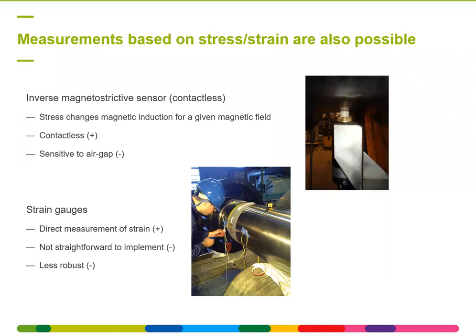Typically, the sensor needs calibration, and this is typically done when going from full speed no load to nominal power. Then you go from zero torque on the shaft line to the nominal torque, and this is used to calibrate the sensor. However, the air gap also changes within this period when going from full speed no load to the nominal load, due to thermal effects, for instance, and so this disturbs the calibration of the sensor. This is one of the reasons why we do not use this sensor anymore, mainly due to these calibration issues.